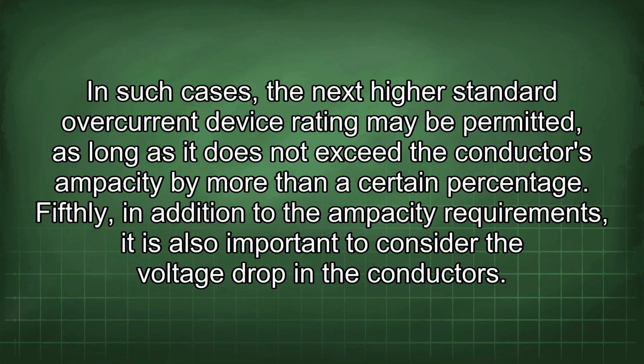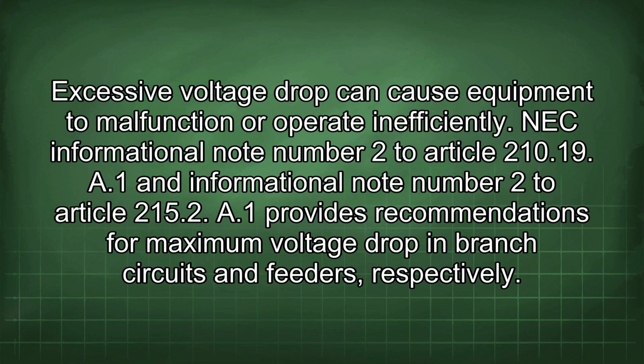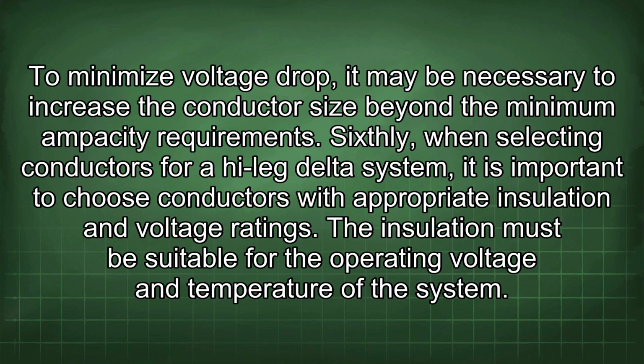Fifthly, in addition to the ampacity requirements, it is also important to consider the voltage drop in the conductors. Excessive voltage drop can cause equipment to malfunction or operate inefficiently. NEC Informational Note Number 2 to Article 210.19 A1 and Informational Note Number 2 to Article 215.2 A1 provide recommendations for maximum voltage drop in branch circuits and feeders, respectively. To minimize voltage drop, it may be necessary to increase the conductor size beyond the minimum ampacity requirement.